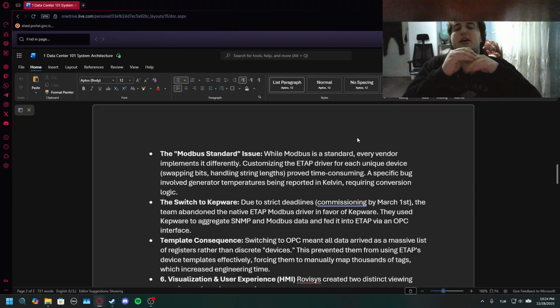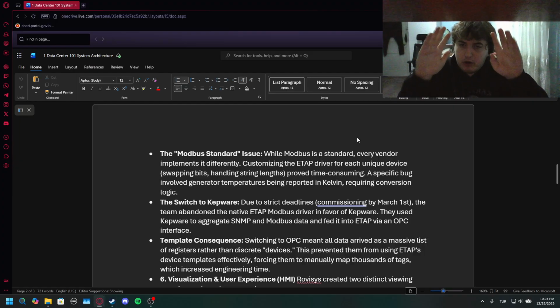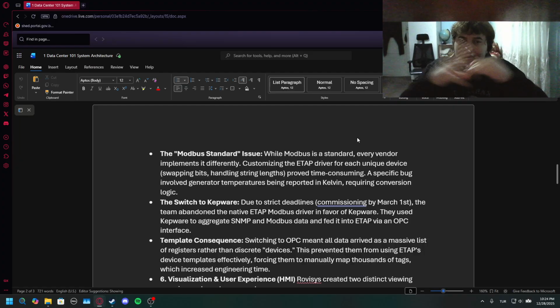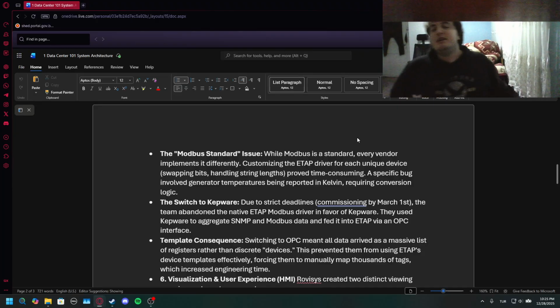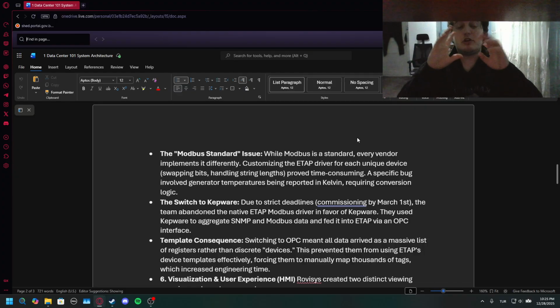So let's say a specific sensor just sends everything in Kelvin, and you need to change that into Celsius. But here's the deal: you cannot change the sensor, so you need to add a small bit of code. This small bit of code is fine, you can just do that, and customizing the ETAP driver is fine too. But this happens with each unique problem - you're not only going to fix one problem, you're going to have more than one.